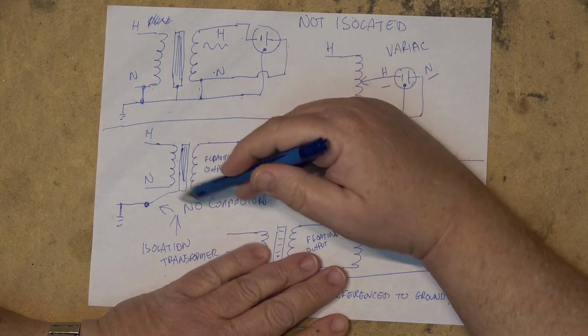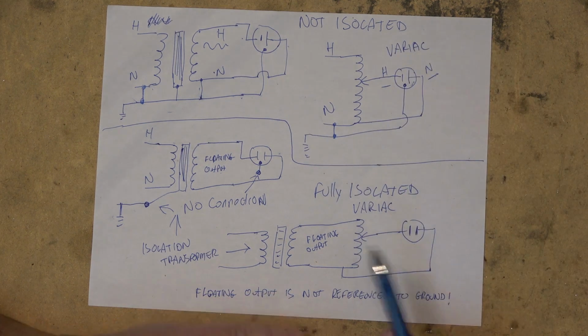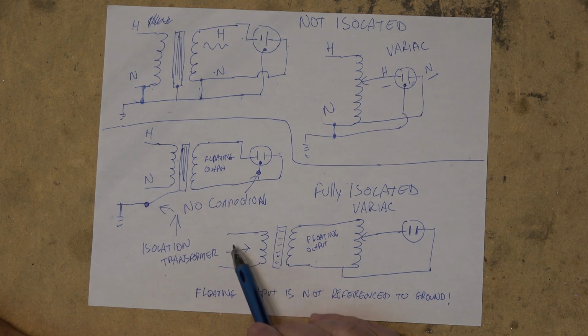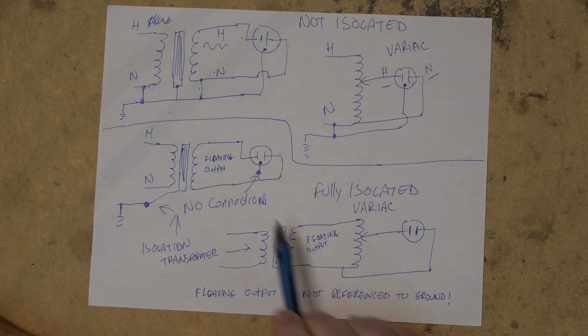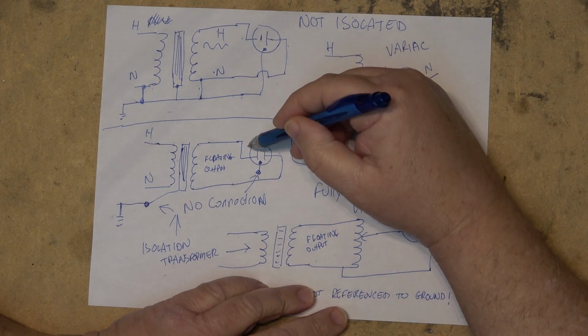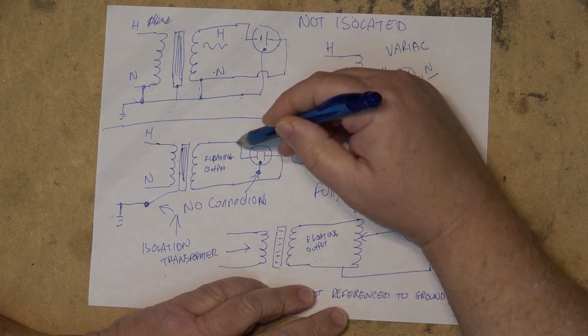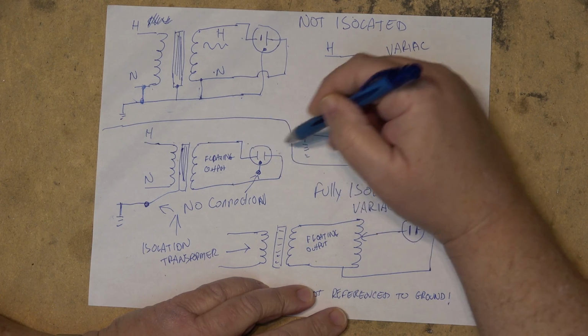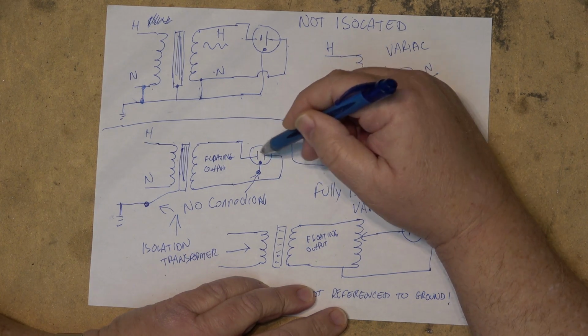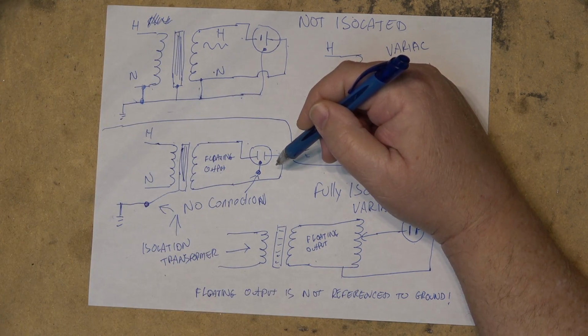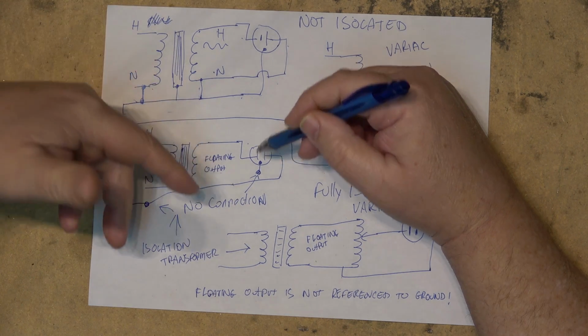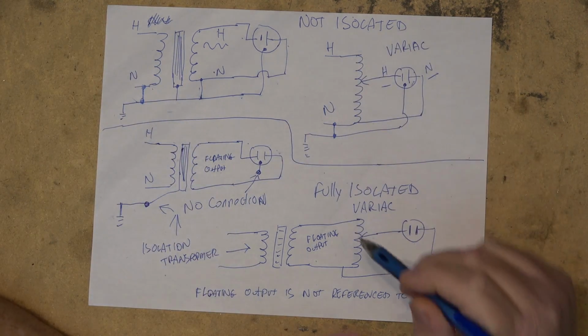This is a true isolation transformer. This is what I use on my test bench. I have an isolation transformer, which has got a floating output. You see, there's no reference. There's nothing marked line or neutral here because there is no line or neutral. In effect, either one can be a line, and then if you were to reference it to a ground, you'll find that the output is floating.